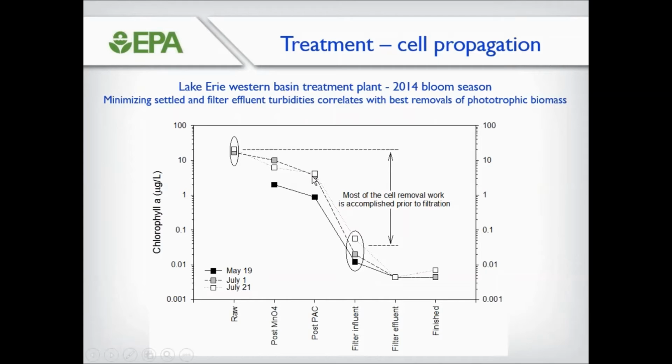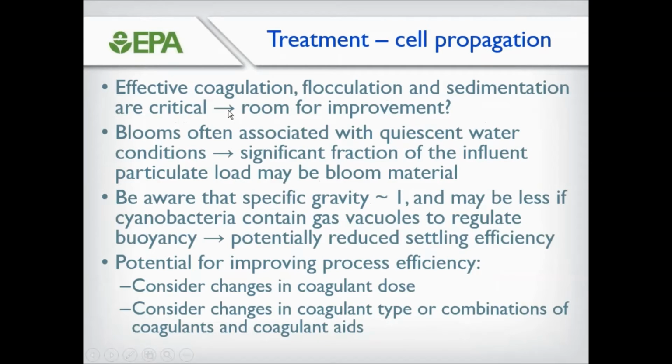And approximately half of that was achieved in the clarifiers. What that points to is that effective coagulation, flocculation, and sedimentation are critical. So for your treatment facility, ask yourself, do I have room to improve my coagulation, flocculation, and sedimentation process?